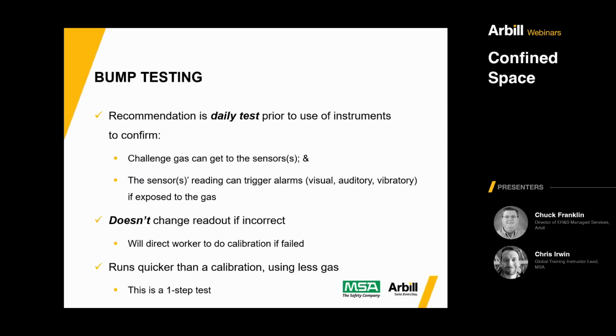There is an additional test that we get into called bump testing. This is a daily check. Now, when I say daily, this would be a pre-use thing. If you're not using a detector on a given day, I would not tell you that you need to do this. But prior to use, similar to inspecting a harness before doing entry or fall protection, you would do this. It's a very, very quick check that makes sure the same gas in that bottle we just looked at is able to get to the sensors and trigger alarms.